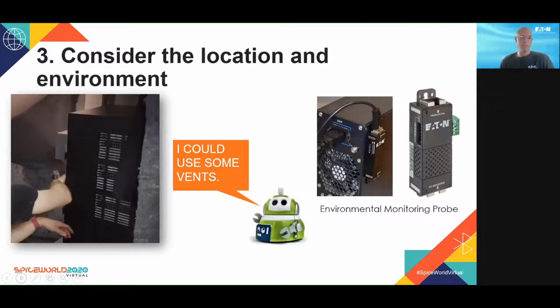And 3, we look at considering the location and environment. And this is in regards to airflow, heat, humidity, and dust. And don't stack stuff on top of the UPS. It gets hot. Never block the ventilation grates. Never expose the system to direct sunlight. Optimum operating temperatures for a lead acid battery is around 25 degrees Celsius or 77 degrees Fahrenheit.